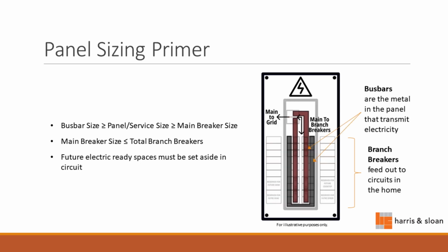If you were at last week's presentation on battery ready requirements, you'll remember one requirement was a 225 amp rated bus bar. That's essentially the metal behind the hood of this panel, rated to meet 225 amps. This is not the same as your service size, though. Your service size provided by the utility is going to either be equal to it, or a little bit smaller, typically 200 amps.